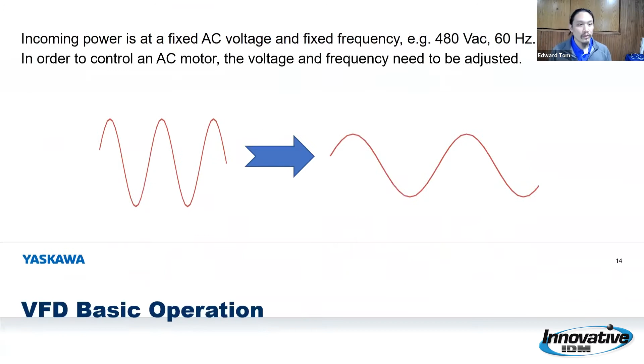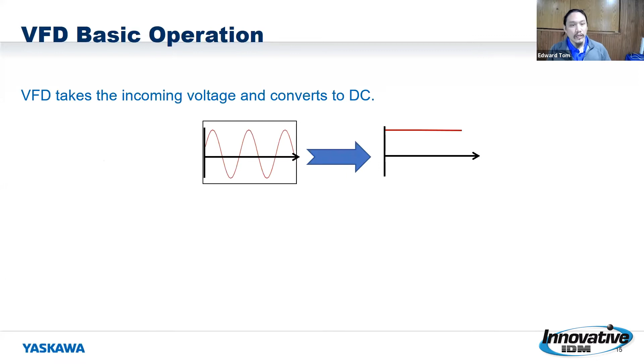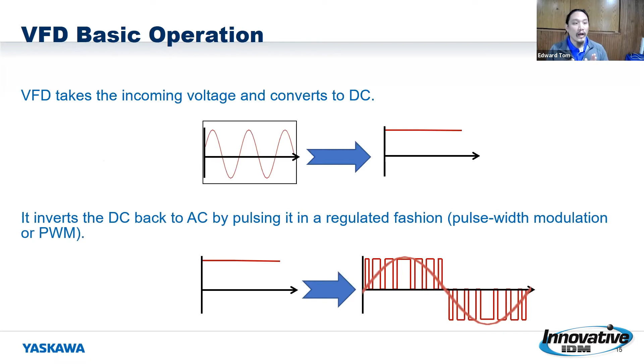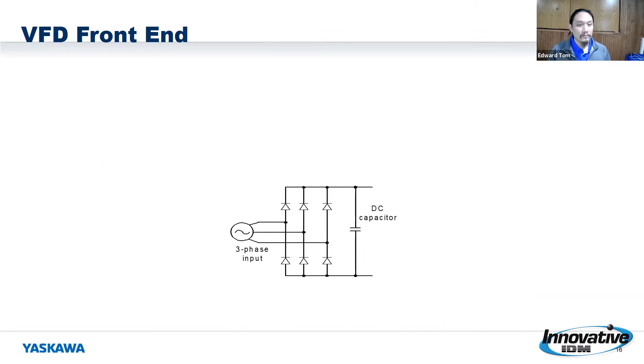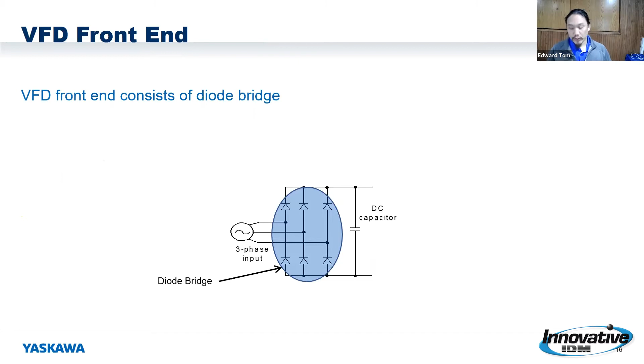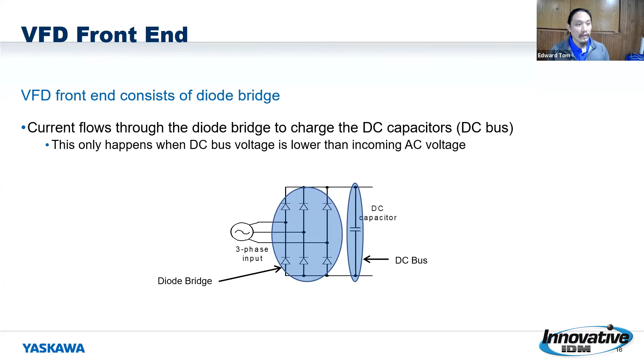Well, I can't really just take the line voltage and manipulate it right on the spot, at least not easily. So when VFD technology was first created, what they did was they took the incoming voltage, that fixed frequency, that fixed voltage, and we take it and we convert it to DC. And from DC, we take that and then pulse it out, regulated pulses, and send that to the motor so that it gets that equivalent voltage and frequency that we want. And the hardware that goes behind it has to do with the diode bridge. And a diode bridge in there is really just like a valve, like a check valve. If the voltage on the front side, your incoming side, is higher, it'll send current over to the DC bus, charges that up. And if it's lower, nothing happens.